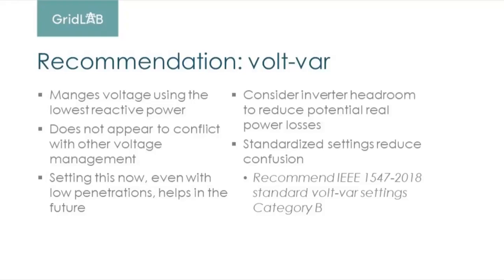And then we think developers and customers should be thinking about adding headroom into inverters to reduce potential real power loss. And the corollary to that is to make sure that utilities are not overly restricting their interconnection requirements, saying, oh, you're installing a 1.1 kVA inverter, but you said it's 1 kilowatt. And yes, that extra kVA is potentially for reactive power. So it's important that the interconnection process allow headroom in the inverters. We think volt-VAR is a pretty uncontroversial recommendation.